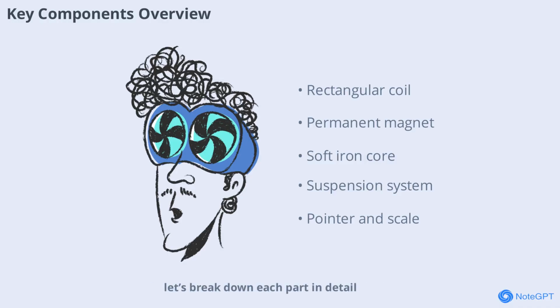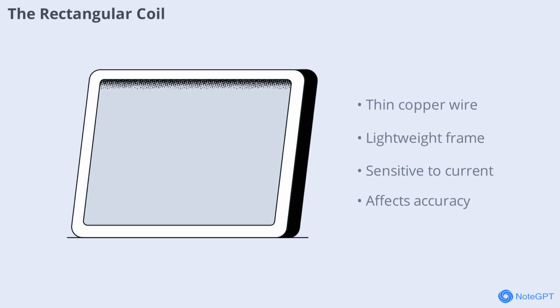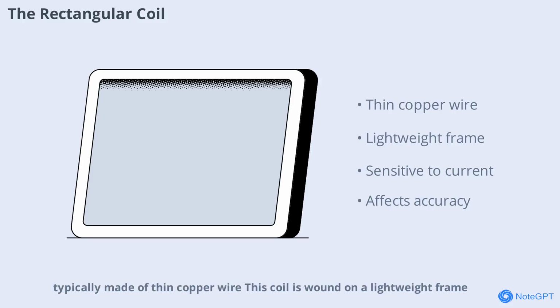Next, let's break down each part in detail. The heart of the galvanometer is the rectangular coil, typically made of thin copper wire. This coil is wound on a lightweight frame to ensure it can move freely with minimal resistance. When electric current passes through the coil, it interacts with the magnetic field, generating a force that causes the coil to rotate. The number of turns and the area of the coil directly affect the sensitivity of the instrument. A well-designed coil is essential for accurate current detection.